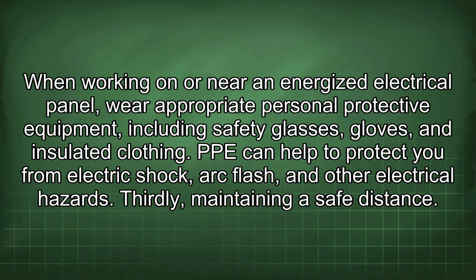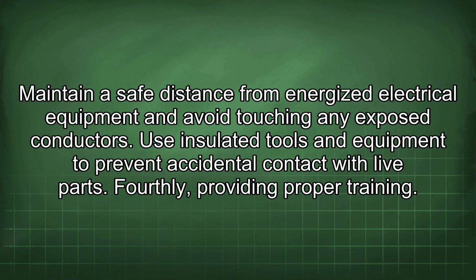When working on or near an energized electrical panel, wear appropriate personal protective equipment, including safety glasses, gloves, and insulated clothing. PPE can help to protect you from electric shock, arc flash, and other electrical hazards. Thirdly, maintaining a safe distance. Maintain a safe distance from energized electrical equipment and avoid touching any exposed conductors. Use insulated tools and equipment to prevent accidental contact with live parts.